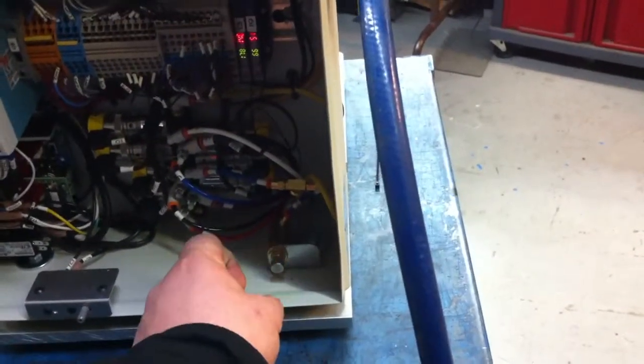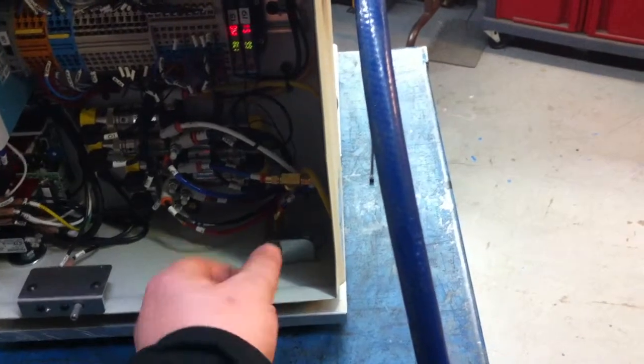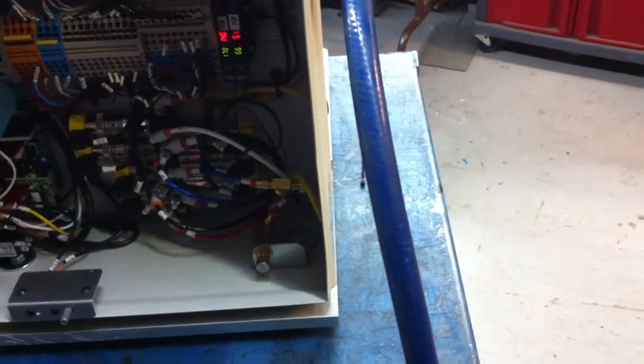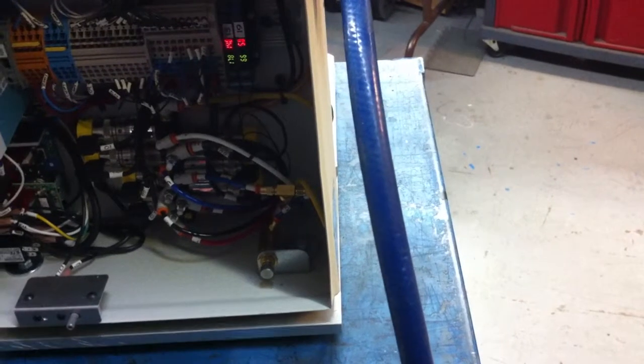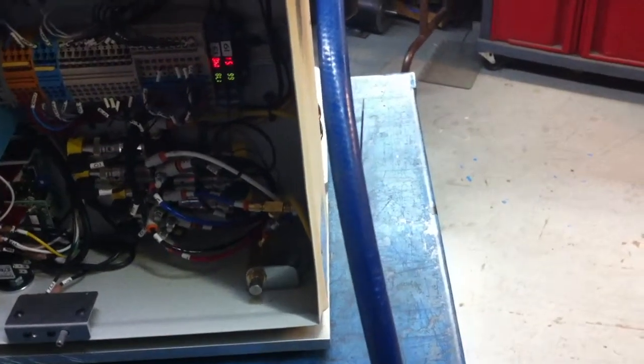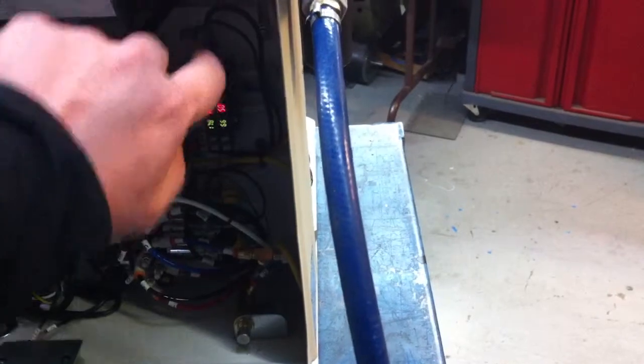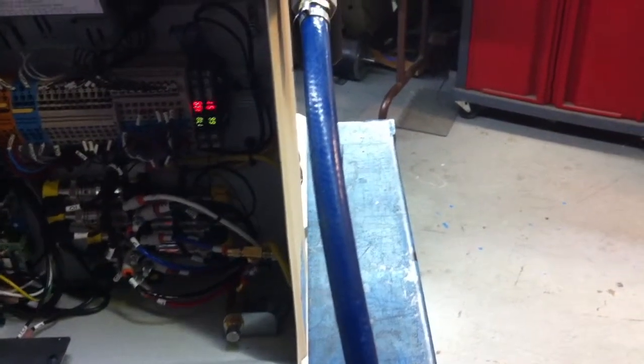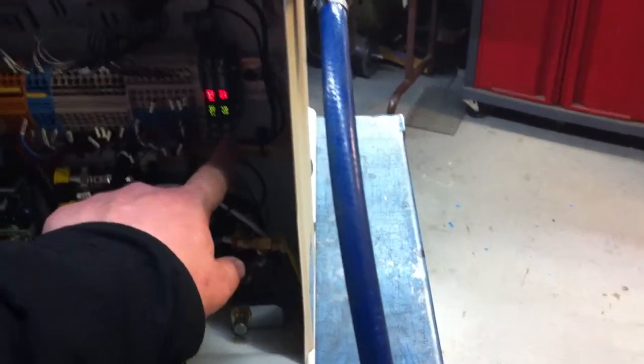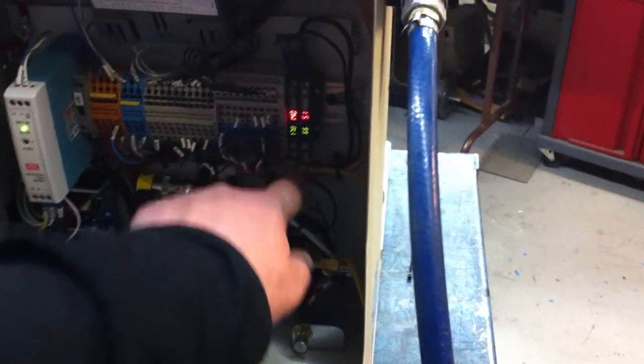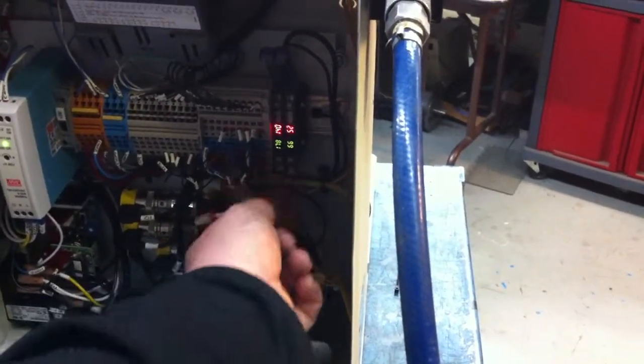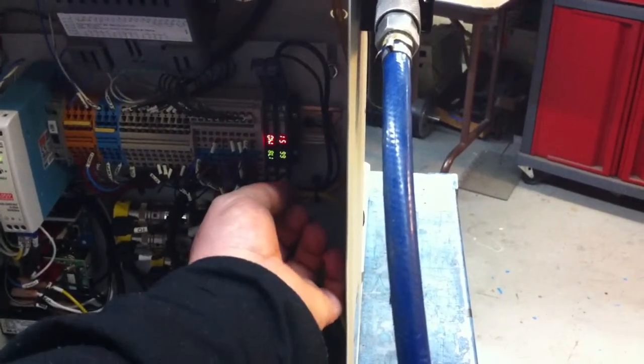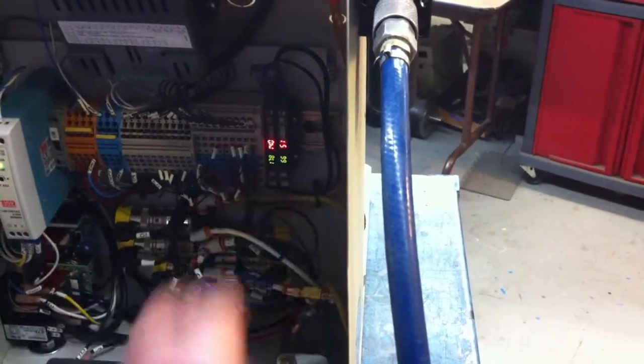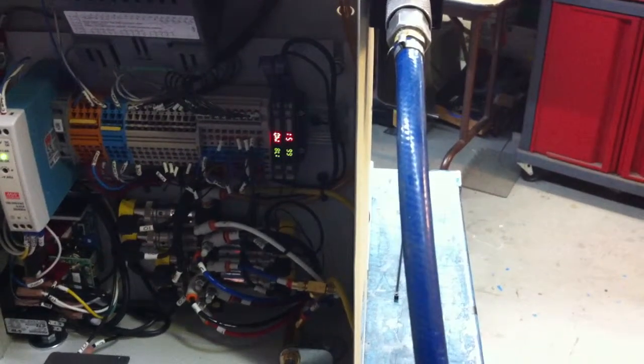Turning that clockwise will increase your pressure. Turning it counterclockwise will decrease it. And again, you want to go really slow with it. Going too far will cause a lot of change. On your fiber optics, they're really easy to set. If you replaced a fiber optic because you broke one or it got damaged somehow, the bottom button right here is what unlocks the fiber optic so it can be disconnected. Be very careful with the fiber optics. Again, they're very fragile. You push the lock back up and that seats it and holds it into place.